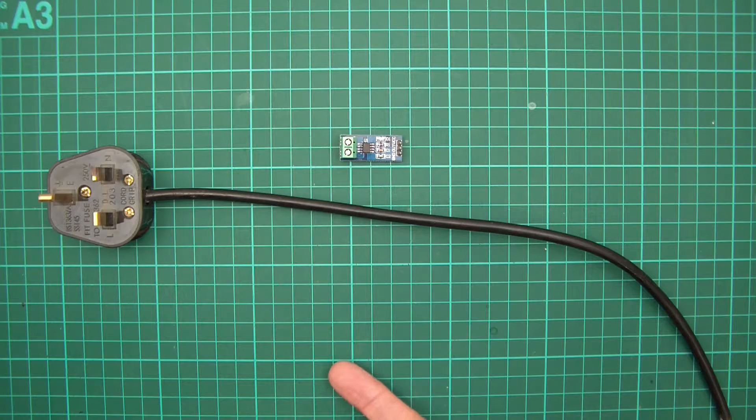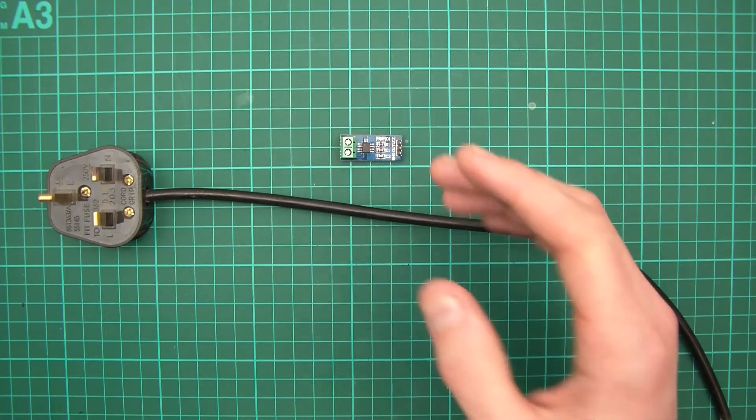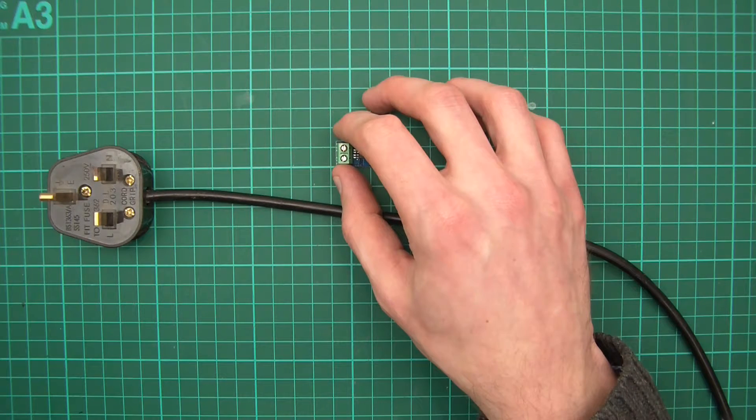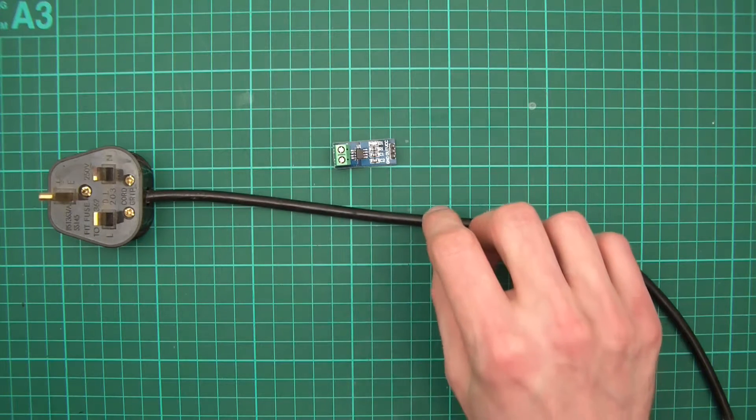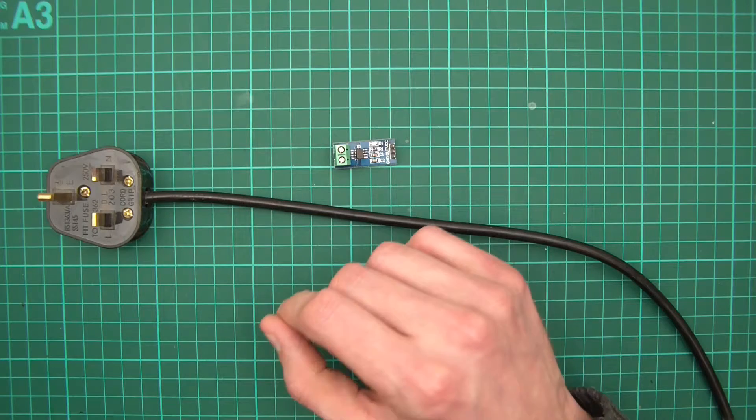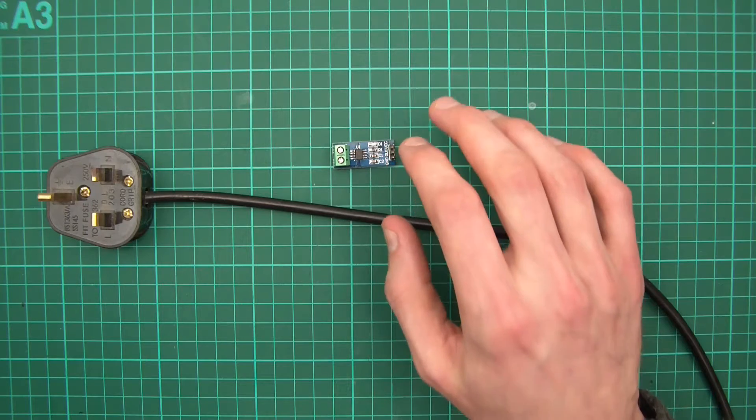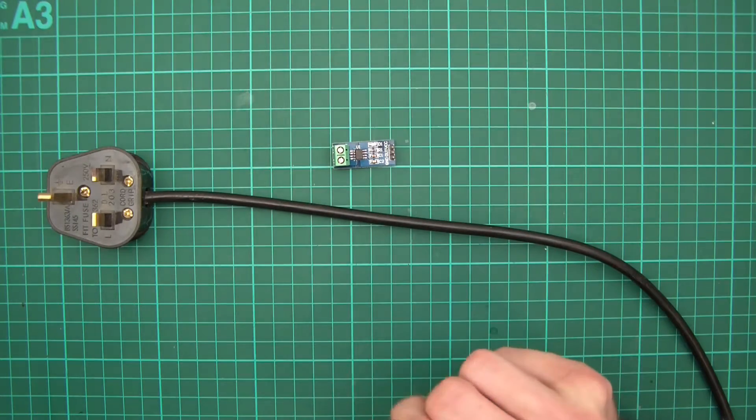Now I'm going to be sure of a few different things when I do it. I've got an RCBO, which is an RCD and an MCB in one. The idea of this RCBO is that if an amount of amperage flows out of the live terminal and it doesn't return through the neutral terminal, this thing shuts off within I think it's 30 milliseconds or something like that. So it's a great safety device, but it's still not safe. You can still get awful shocks and you could still kill yourself potentially, so just don't do it.